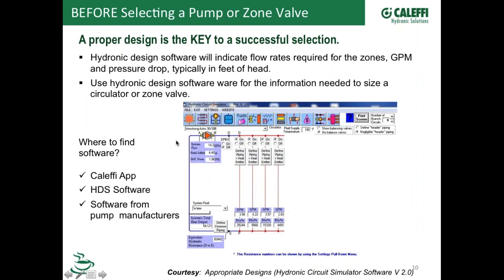Now, I know that a lot of the pumps now are multiple speed, and we've got variable speed pumps, so you've got a little bit more flexibility that you don't get the exact right pump. But you want to at least have a good idea what that pump's going to do to that circuit when you put it in there as far as the amount of pressure it's going to add to the system and certainly the flow rate, so you don't get out there and find yourself undersized.